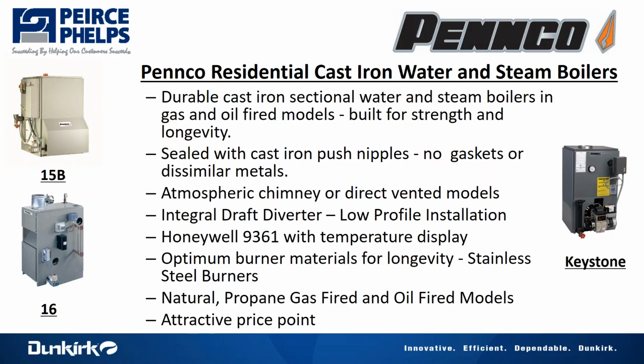Durable cast iron, bulletproof, built for strength and system longevity. Some of the systems that we have here have standing radiation, high water volume, and a lot of scale and sediment in the system. Cast iron boilers are forgiving of those types of systems. We seal our cast iron boilers with cast iron push nipples: the same expansion and contraction rate, a very reliable way to seal our cast iron sections. No gaskets, no dissimilar metals. So it's a nice, robust way to seal the equipment.